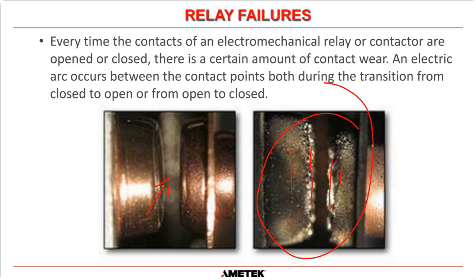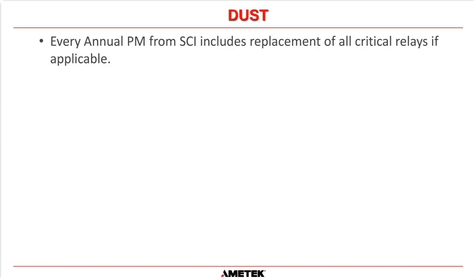They're not going to make a really good flush contact when they close. So as part of our annual maintenance, AMETEK SCI includes the replacement of all critical relays in your system, if applicable. That doesn't mean we replace all of the relays in your system on an annual basis. What it means is all the critical ones that are to do with the operation to keep your load circuits maintained on inverter, all of those will be replaced on an annual basis. And from those pictures, you can see why.